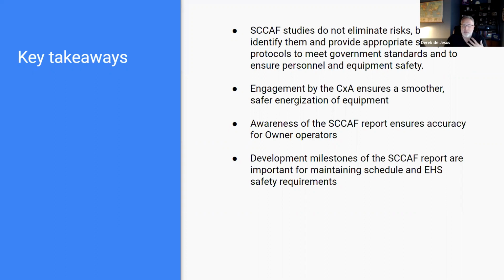The first thing I always reference when I do a design review is I start with the one lines, the electrical one lines, and I start to look at the pieces of equipment that we have. I'm verifying breaker sizing. I'm looking for characteristics such as long time, short time, instantaneous ground fault. I'm looking at relays. Then I jump into the power study spec.